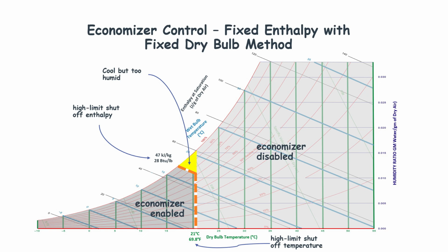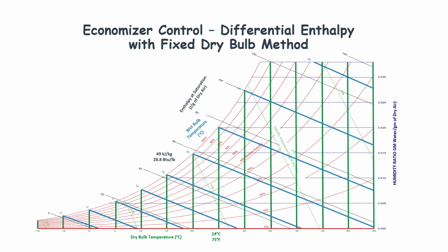The fourth control method is differential enthalpy with fixed dry bulb. This is the most complex method, and in theory, this is the most accurate one because it provides the maximum energy saving and maximum comfort for people. In this method, the controller compares the outside air's enthalpy with the return air enthalpy, and also the outside air's dry bulb temperature with a programmed high limit shutoff temperature.